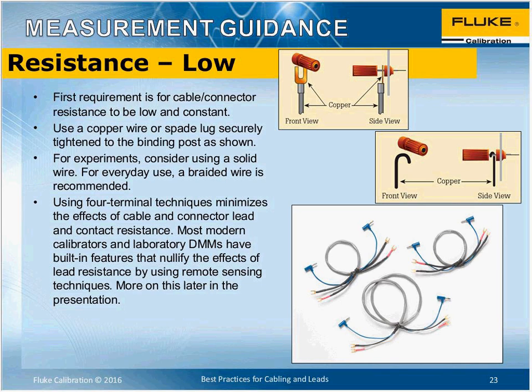The resistance, low resistance measurements. This is a problematic measurement if you don't use the correct cabling. What we recommend is a copper wire or spade lug securely tightened to the binding post. You're not going to want to use the banana jacks for this. So we typically recommend either a copper wire, as shown there, wrapped around the terminal, or a spade lug connection. As we just talked about with dissimilar metals, it takes time to stabilize. Some leads themselves have a soldered connection and also have dissimilar metals. There could be issues, but just take your time with this measurement. Using 4 terminal techniques minimizes the effect of cable and connector lead and contact resistance. We're going to discuss that in a moment, 2 and 4 wire compensation, and it does help with the measurement.